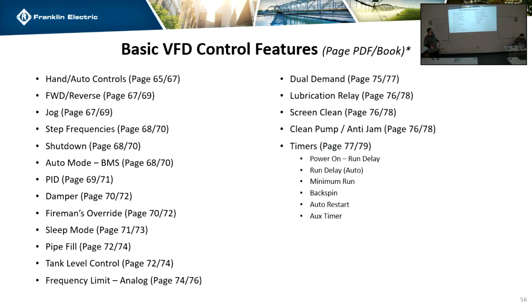Most of the time, if the drive is supposed to be smoke clearing, and the Fireman system comes on and tells it to clear smoke, you don't want a run command also, because someone might have the switch in auto with that signal not on, or in hand, and if it goes to Fireman's override, the drive should ramp up. So you would set it to run without the run command, which means all it has to see is Fireman's override. If you want a double layer of protection, you can set it so that it runs with the run command, and it just means it has to see two signals. So there's one signal versus two signals.